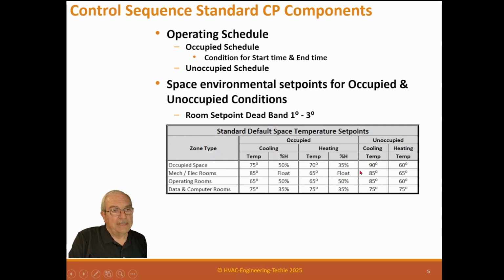The only thing about temperature and humidity set points is you should encourage the operators to keep them common throughout the building. In other words, don't have one zone at 72 degrees and the next zone at 78 degrees, because any interaction of temperature is going to cost you energy. The same with humidity, it may be even worse. You don't want to be putting it in one place and taking it out another place. That's just wasting energy, so you want to have it the same. I've always liked to see operators have a policy that says our set points are 75 or 78 degrees, and that's it. If you want it to be 60, that's not going to happen. It's going to be 78. That's our standard across the building.